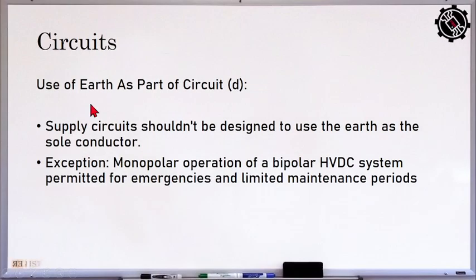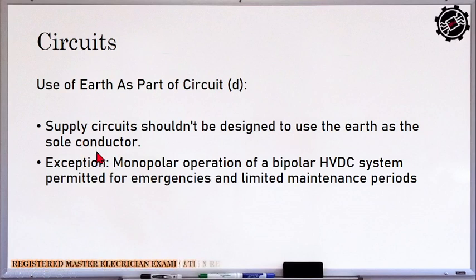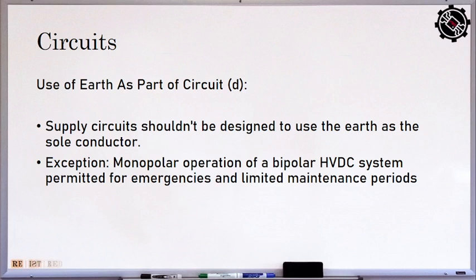Okay, then use of earth as a part of circuit. So supply circuit couldn't be designed to use the earth as the sole conductor. So hindi ibig sabihin kasi underground siya tapos yung metal part natin nakadikit na doon sa earth, nakalibing na siya, ibig sabihin grounded na yon. So hindi yun acceptable. So you must have a wire na yun yung gagamitin as the grounding system, no? So tapos mayroon pa ring grounding electrode. So the exception for that one is the monopolar operation of a bipolar HVDC, a high voltage DC system, no? Yun lang, no? So that is for emergencies and limited maintenance periods, no?